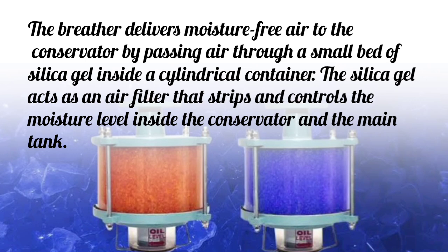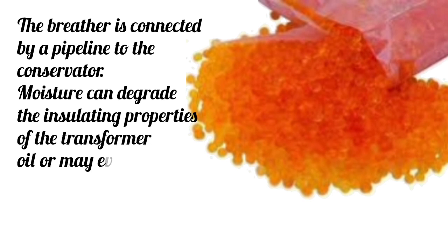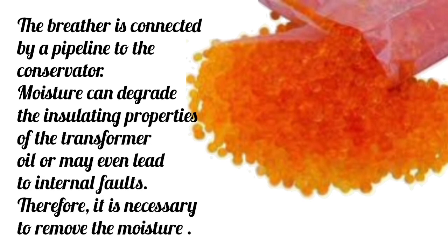The silica gel acts as an air filter that strips and controls the moisture level inside the conservator and the main tank. The breather is connected by a pipeline to the conservator. Moisture can degrade the insulating properties of the transformer oil or may even lead to internal faults. Therefore, it is necessary to remove the moisture.